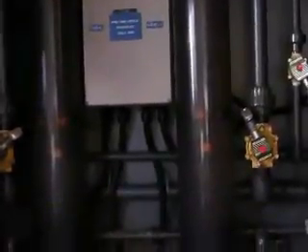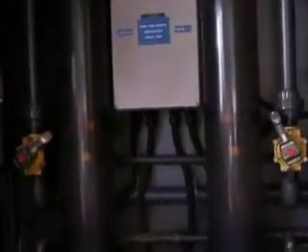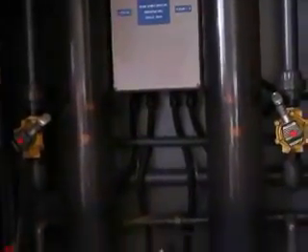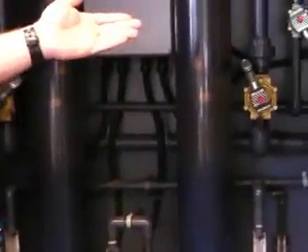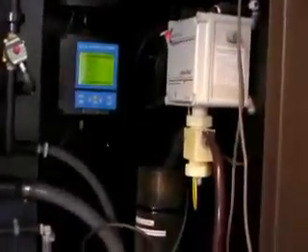We have the turbidimeters that we use for our combined turbidimeters. This was our little invention here. The output is kind of cool. You can work with stuff like, let's say, a piece of equipment doesn't quite do what you need. You have room out here if you're smart about it to make it work, as long as it stays within certain parameters. For example, we have to run a minimum 3 gallons a minute. So we have this little tube that we can adjust, and it makes our operators, you know, they can get going, if it gets to this point in 1 minute, shut it off, it's ready to go.